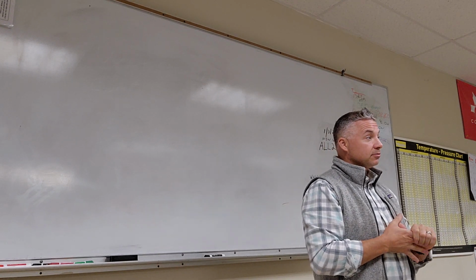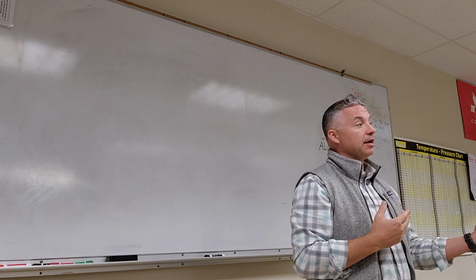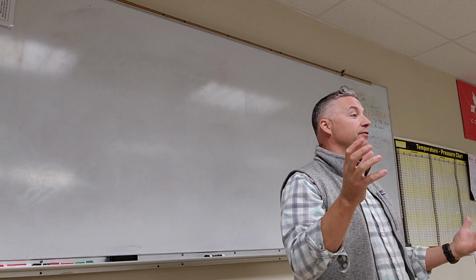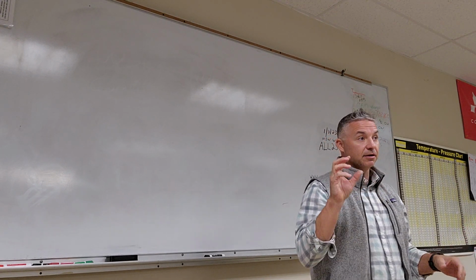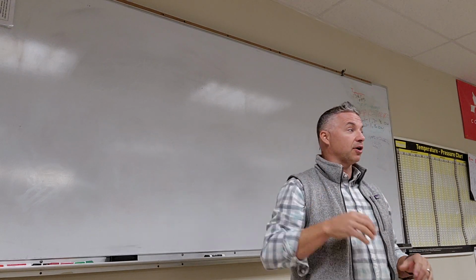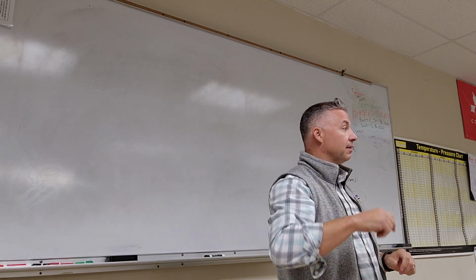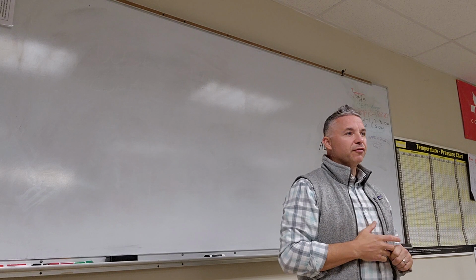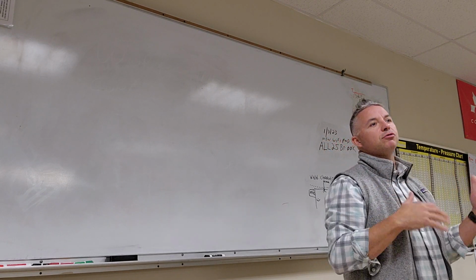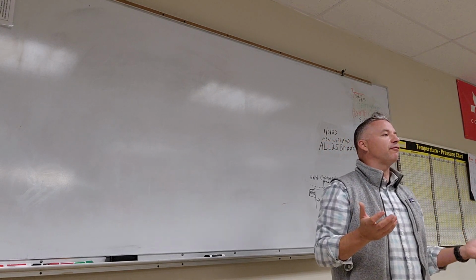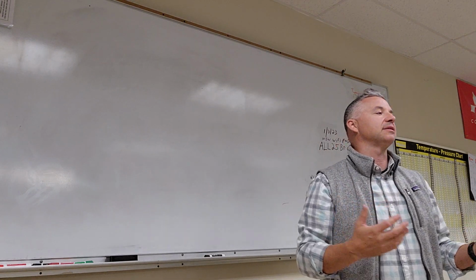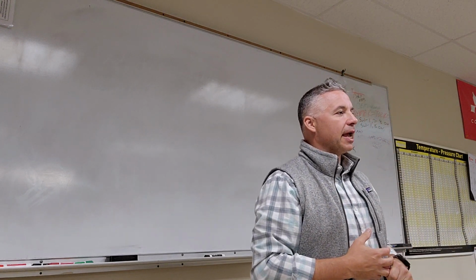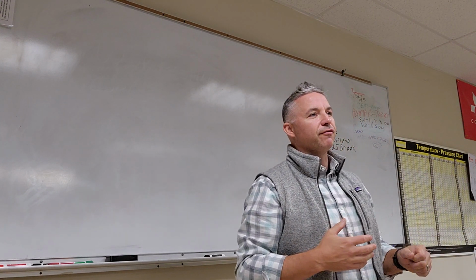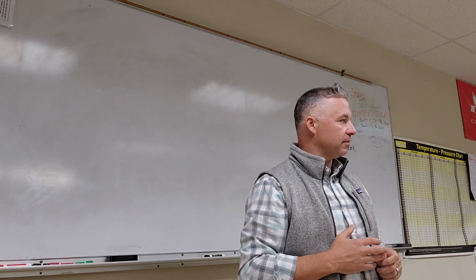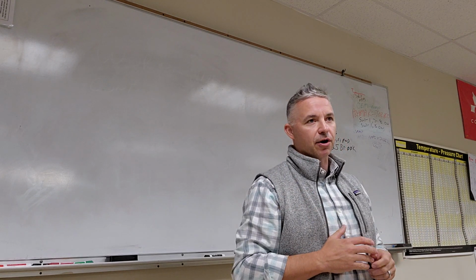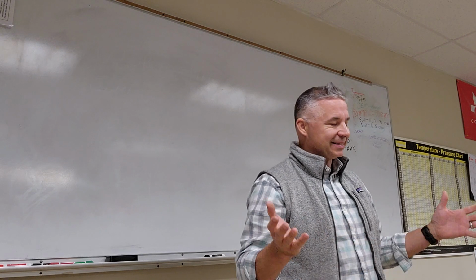On the Aprilaire? No. Current sensing relay, and then a humidistat. And very oftentimes, the ones that you guys are maintaining, you're going to see that humidistat in the return ductwork. And we're going to set that 35, 45%. With those Aprilaire flow-throughs, you really don't run the danger of over humidifying or causing too much damage inside the system. So it's okay to just turn those things at 45, make sure they go on and off with the fan. They shouldn't run if there's no fan running, okay? But that's the simple system.